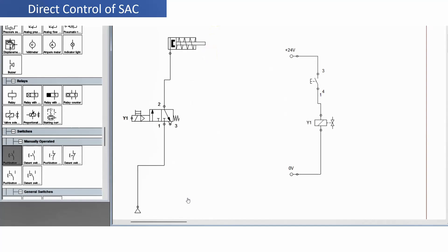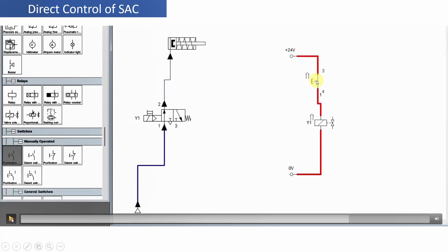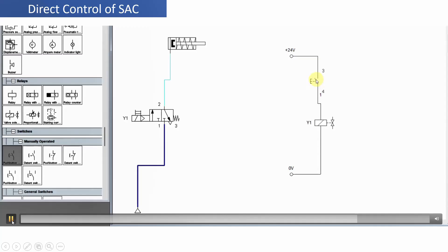You can see the various components which we have already discussed are now shown here. Now run the simulation. Once you press this particular switch, the circuit will be completed, the solenoid valve will get energized, and it will operate the solenoid operated direction control valve into the left envelope mode. Compressed air will flow from port 1 to port 2, causing the piston to move in the forward direction.